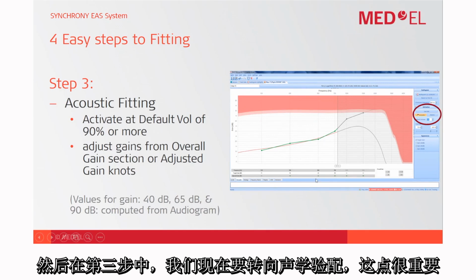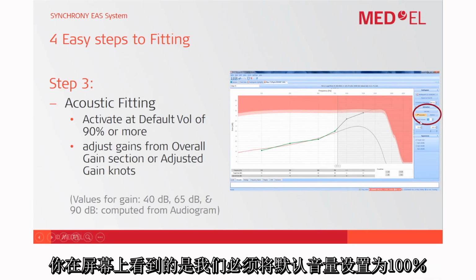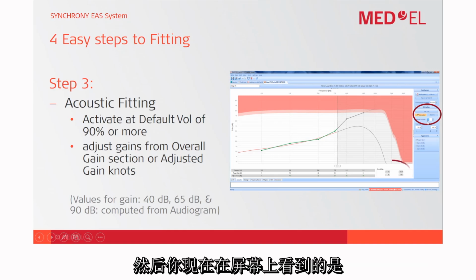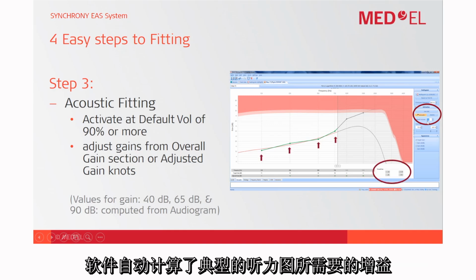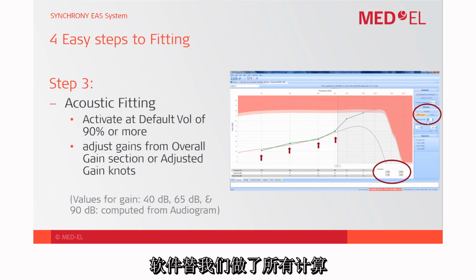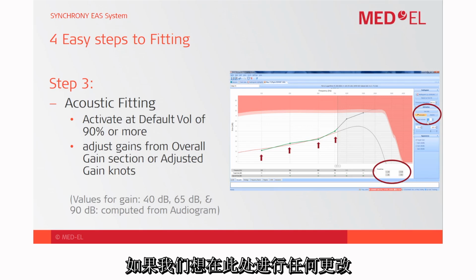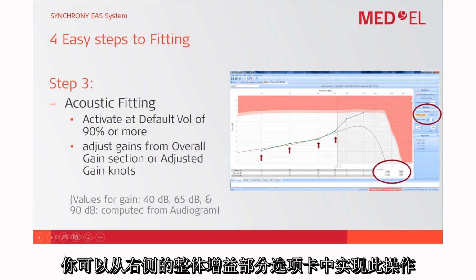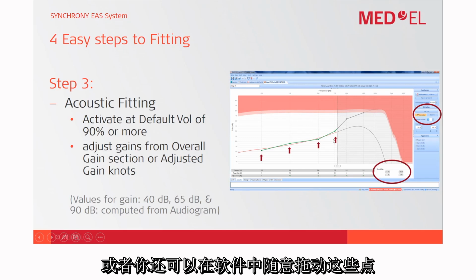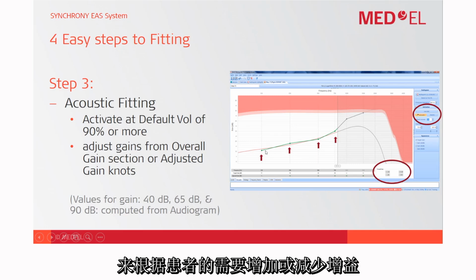And it is important here, what you see on the screen, that we have to put the default volume to 100%. And what you see on the screen right now is that the software has automatically calculated the gain which is required for the typical audiogram which was fed to the software. So the software has done everything. If we want to make any further changes here, you can do that from the overall gain section tab on the right here, or the software also gives you the flexibility to drag these knots so you can increase or decrease the gains as desired by the patient.